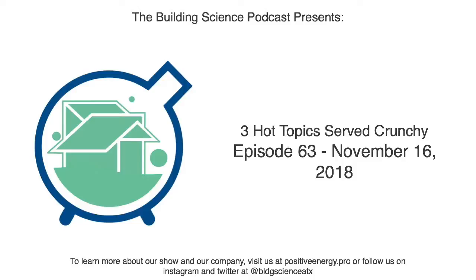Right. Yeah. I think the data that I've seen from real-world applications of those units, especially when they're used just for water heating, which is mostly what they're designed for, is fantastic. And with the Sanden split system, you definitely have faster recovery times. With the large tank, you have 80-some gallons of actual storage, whereas with the American manufacturers, 80 gallons really means 72. Did you know that? I did not know that. How come? Why are they allowed to be 10% under on their actual storage compared to what they say it is? Oh, fascinating.